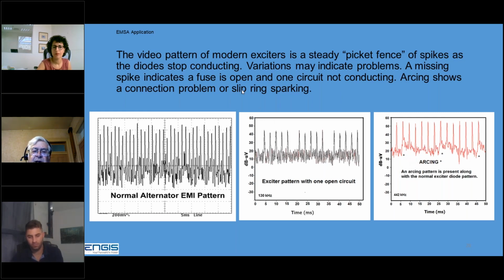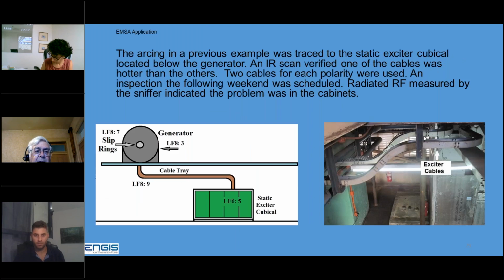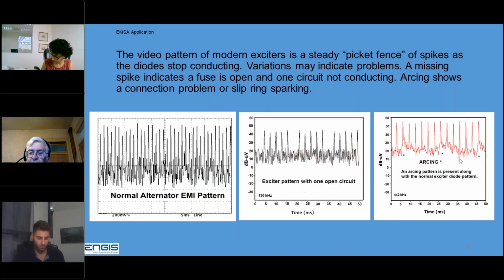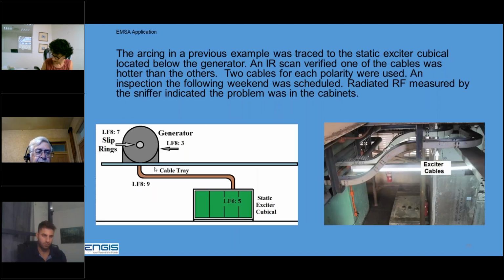So is it in the slip ring if it's an alternator type exciter, or is it a bad connection in the brushless exciter itself, or is that the slip rings? Here is one down in, I think this was in the Dominican Republic. We picked up this pattern here. So we knew we had arcing.